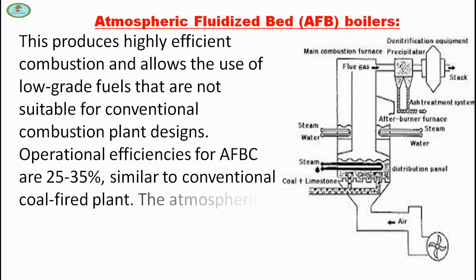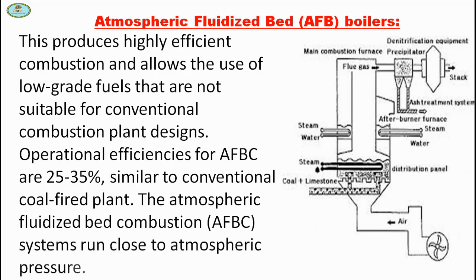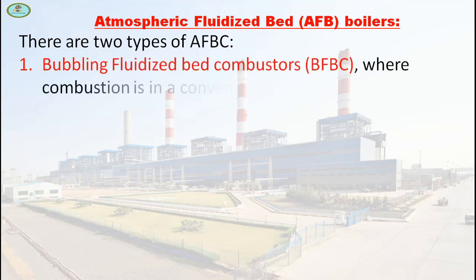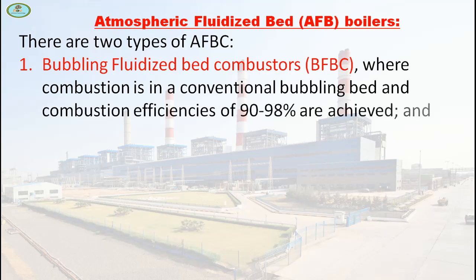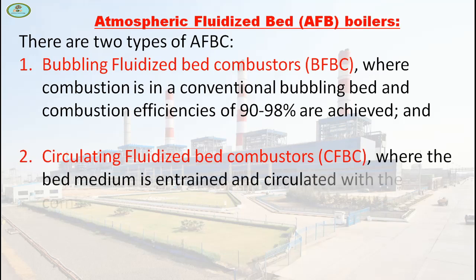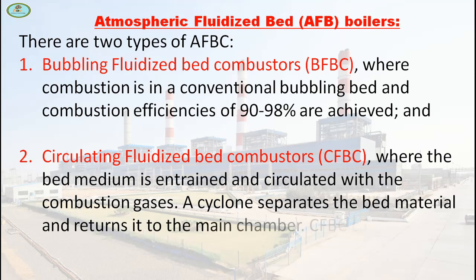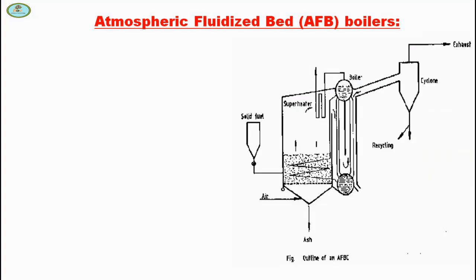Similar to conventional coal-fired plants, atmospheric fluidized bed combustion systems run close to atmospheric pressure. There are two types of AFBC boiler. The first is bubbling fluidized bed combustion, BFBC, where combustion is in a conventional bubbling bed and combustion efficiencies of 90 to 98% are achieved. The second is circulating fluidized bed combustion, CFBC, where the bed medium is entrained and circulated with the combustion gases. A cyclone separates the bed material and returns it to the main chamber. CFBC can achieve combustion efficiency greater than 98%.